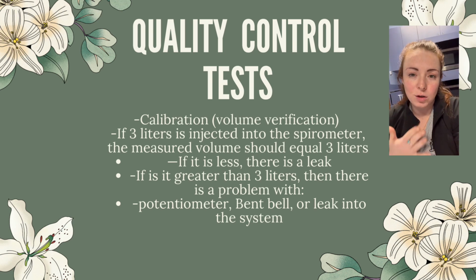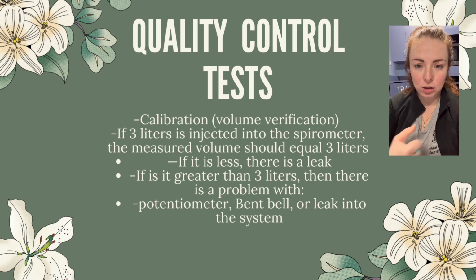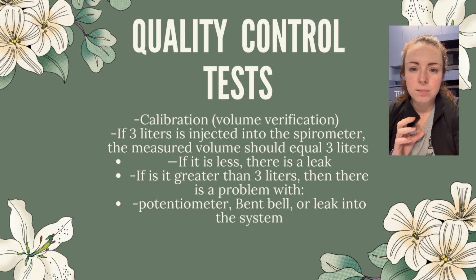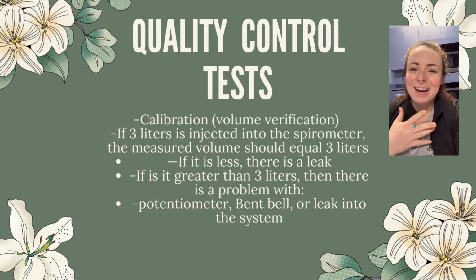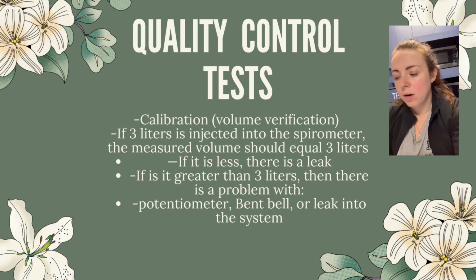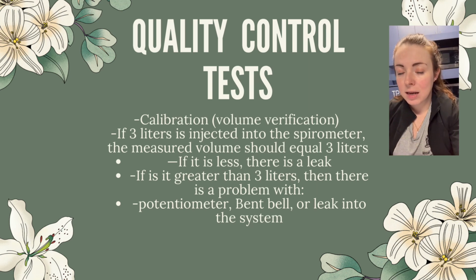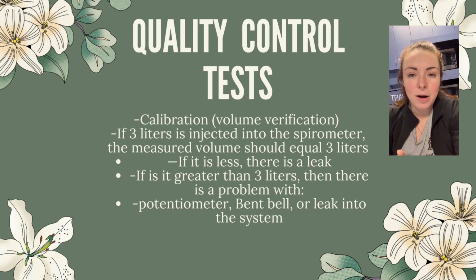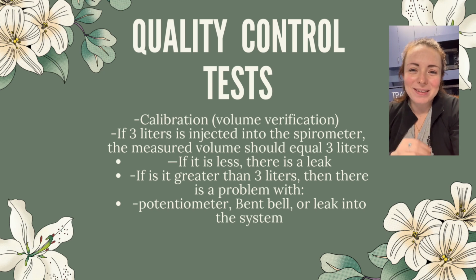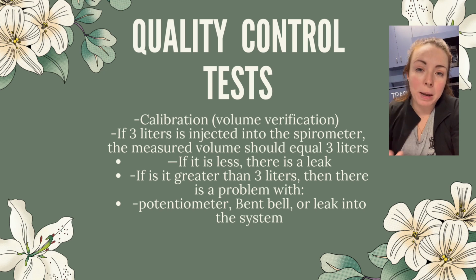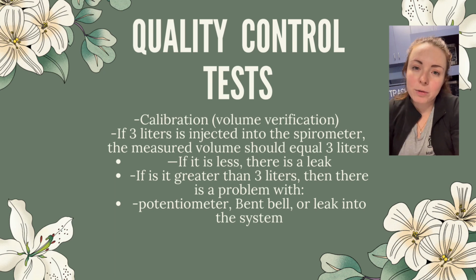So if 3 liters is injected into this spirometer, the measured volume should equal 3 liters. It's kind of like this long thing that you push and then pull back. It's a pretty cool tool that they use to calibrate. So if it is less than 3 liters, then that indicates a leak. If it's greater than 3 liters, then that would indicate some other problem, like a bent bell, a leak in the system, or a potentiometer. The severity of the 3 liters, depending on if it's less or greater, kind of shows what the issue might be, and then the respiratory therapist can troubleshoot from there.